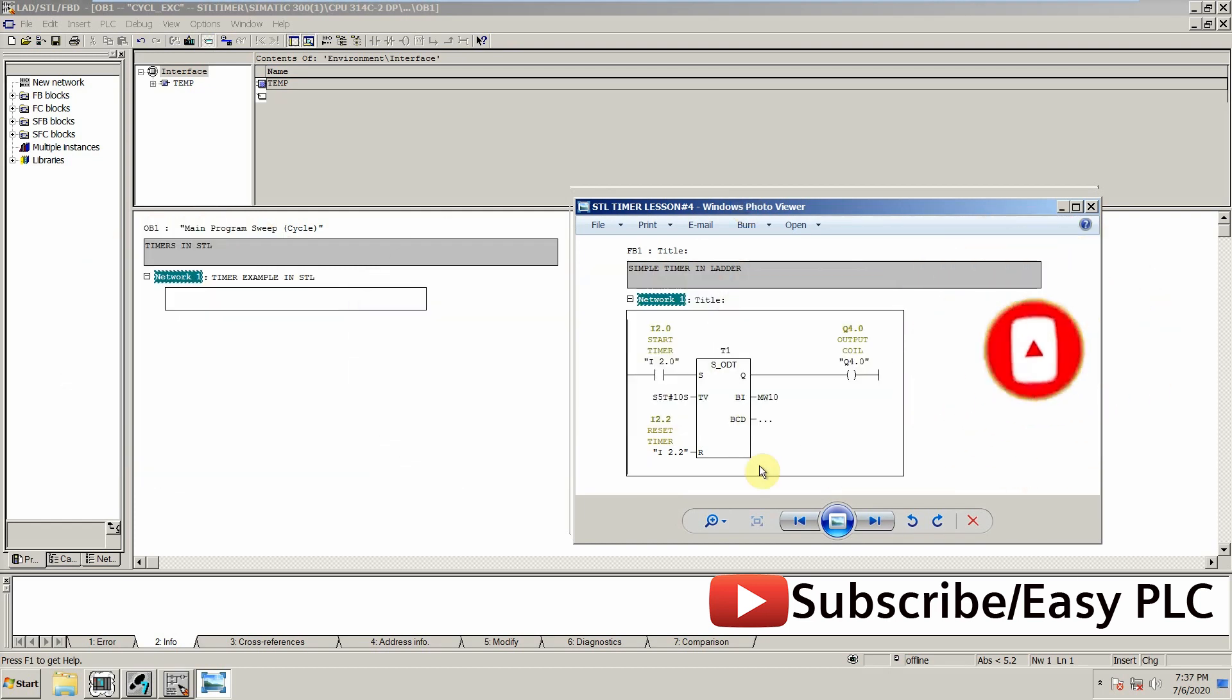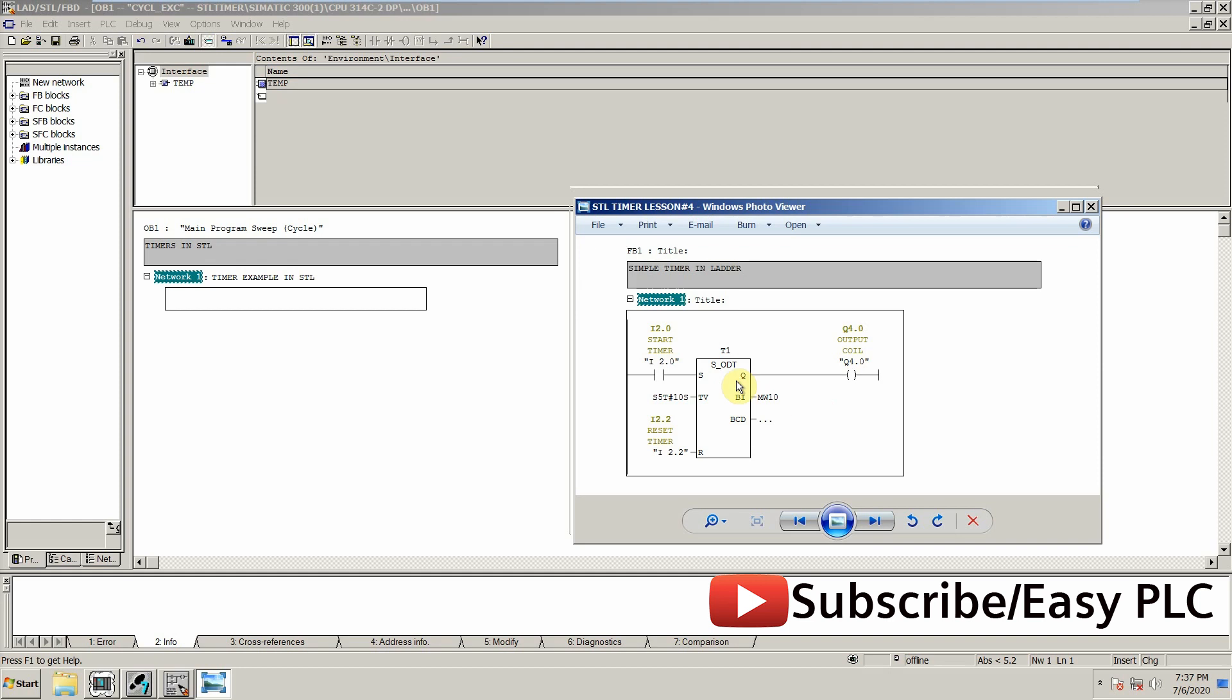As you can see there, I have written a code in ladder logic for the timer T1, and it is an on-delay timer starting by I2.0. Its preset value is 10 seconds and we can reset this timer by I2.2 input, and its output will be Q4.0. Its current value will be saved in memory word. So let's see how we can write a code in STL language for this timer.